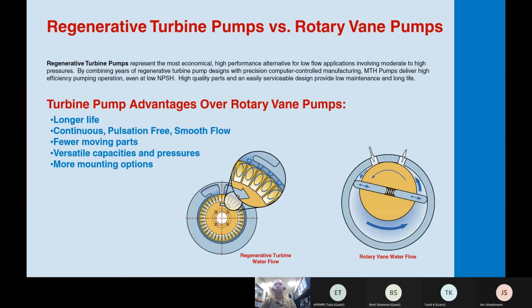So, another one, rotary vane. That's the other one. A rotary vane has pulsation. Where you're going to find a rotary vane pump that we can replace is in a Procon. So we have a small model we call a T31 or a P31, and the smaller models are good to go after with a Procon pump, because a Procon is a sliding vane, and the sliding vane has moving parts. I believe the wiper vanes are either rubber or some kind of silicon, and they will wear out, and they use springs.